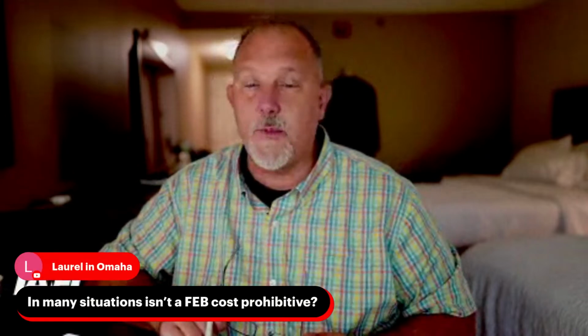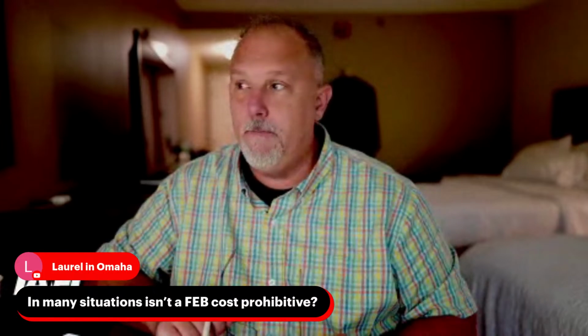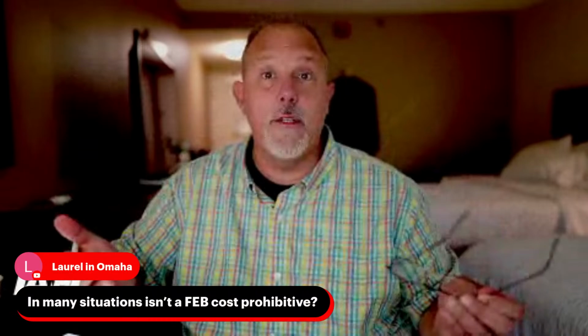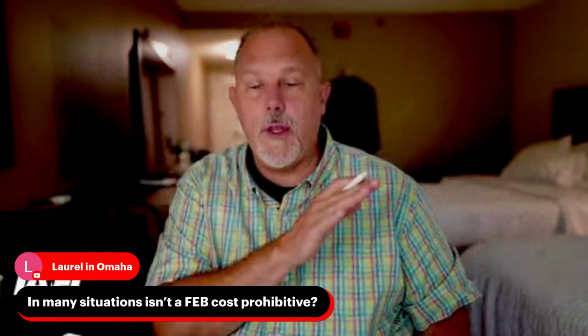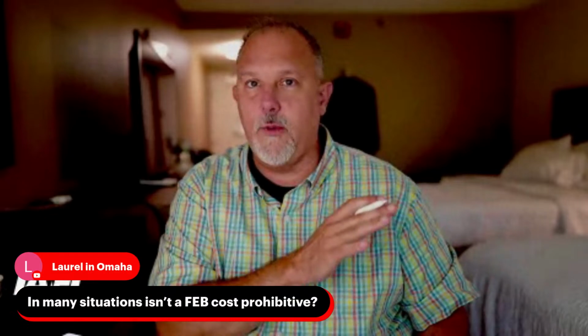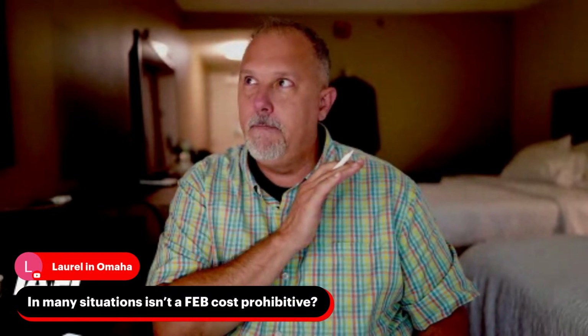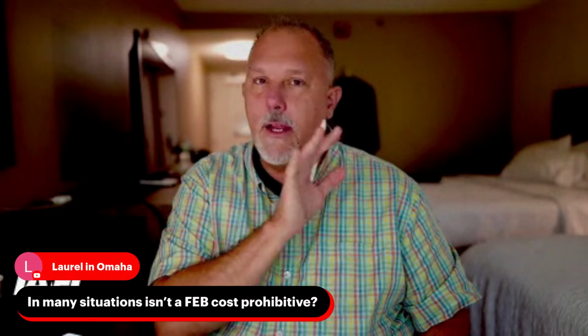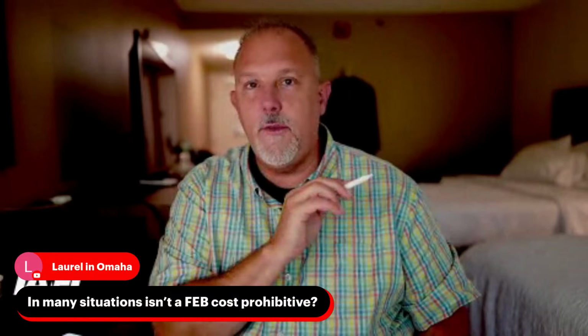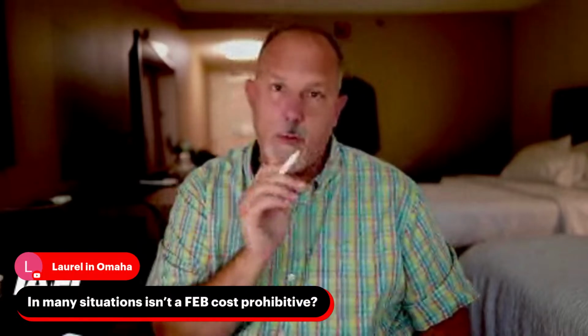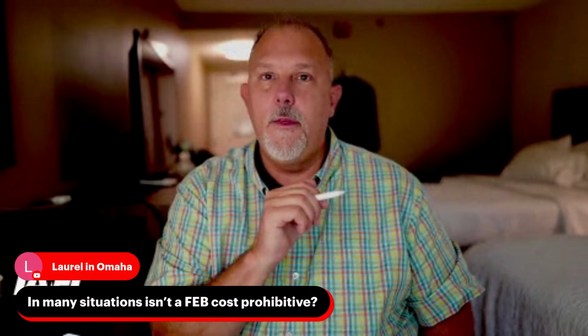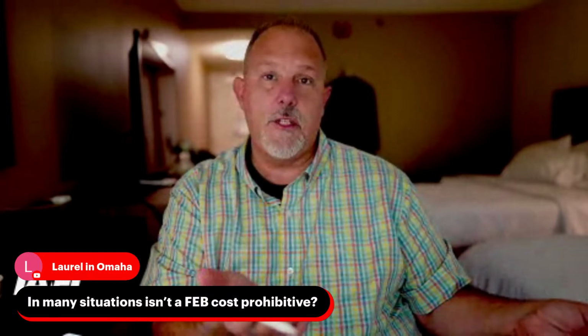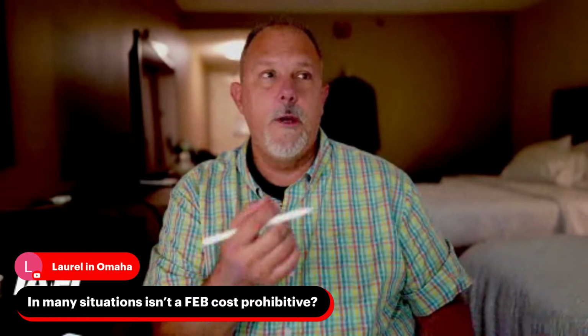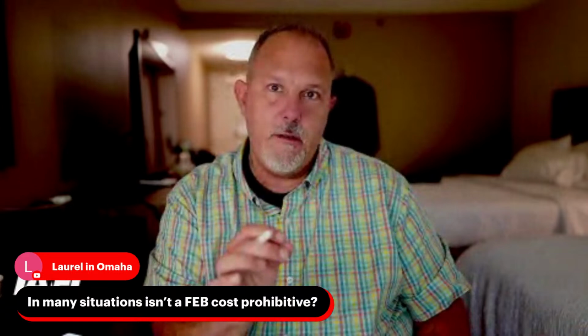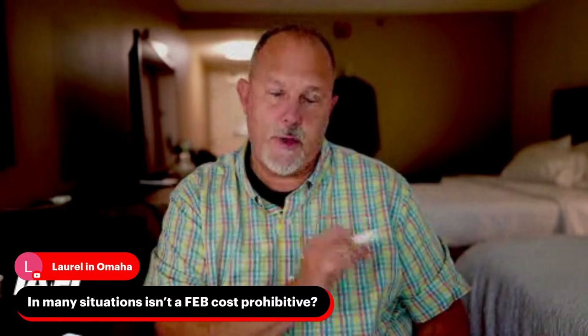So Laurel says, in many cases, isn't the FEB cost prohibitive? And I would say, no, Laurel. You have to weigh what are the differences. If I popped a hole inside of a panel board service equipment, and the inspector says you just compromised the listing of that product, he wants, or she wants, a field evaluation. If that's $1,500, that panel board or that switchgear could cost you thousands. So I think it's a misconception that field evaluations are cost prohibitive.